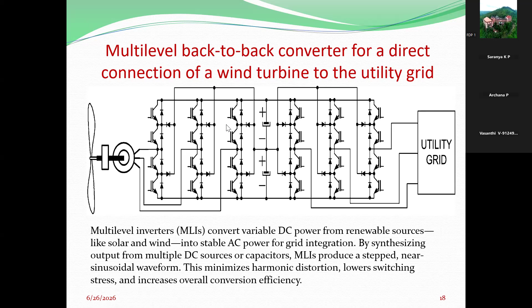It also increases overall conversion efficiency. The key advantages are enhanced power quality, because total harmonic distortion is reduced, limiting impact on grid infrastructure and connected devices. There's also high voltage tolerance, distributing voltage stress across multiple lower-rated semiconductor devices, since multi-level inverters use many switches with lower ratings, limiting stress across the devices.